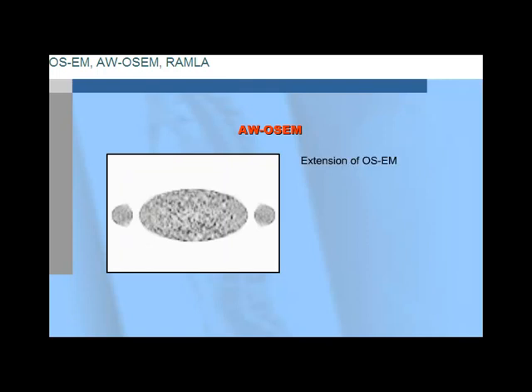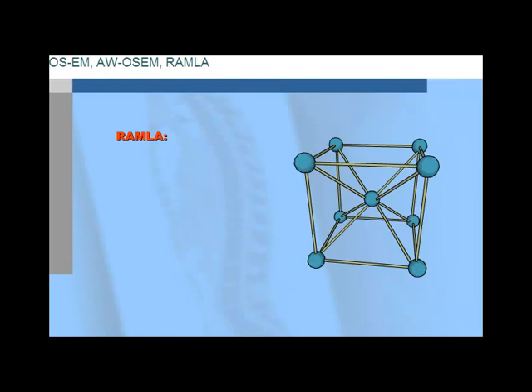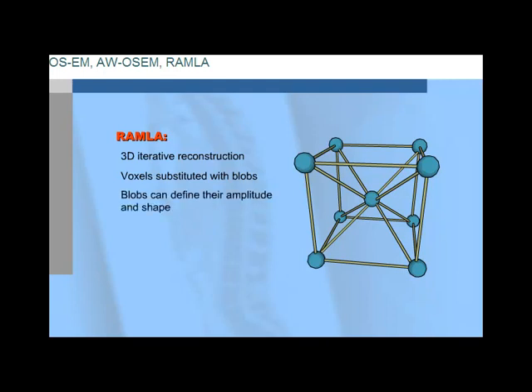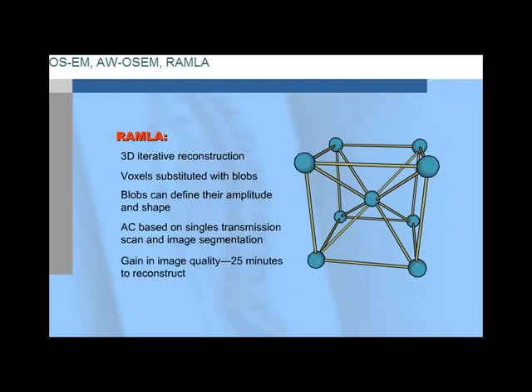AWOSEM is simply an extension of the OSEM technique, with the added capability of weighted LORs that pass through the more highly attenuated areas, thereby addressing artifacts detected in the more commonly found OSEM algorithm. Finally, there is RAMLA, or Row Action Maximum Likelihood Algorithm. This 3D iterative image reconstruction algorithm substitutes voxels with spherically symmetric volume elements called blobs and places them on a uniform 3D grid. The advantage of blobs is their ability to find their amplitude and shape, thus impacting reconstruction image quality. Attenuation correction, incorporated in the algorithm, is based upon a singles transmission scan followed by image segmentation. RAMLA provides a small gain in image quality; however, it requires up to 25 minutes to reconstruct the image volume.